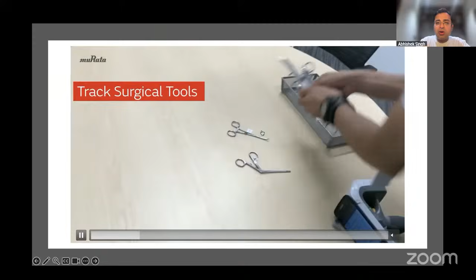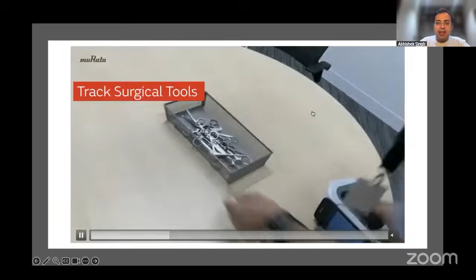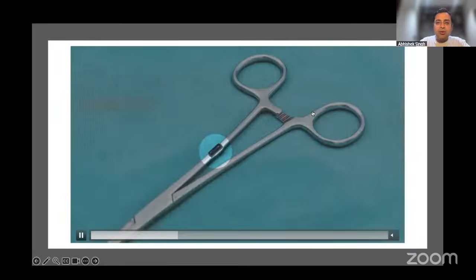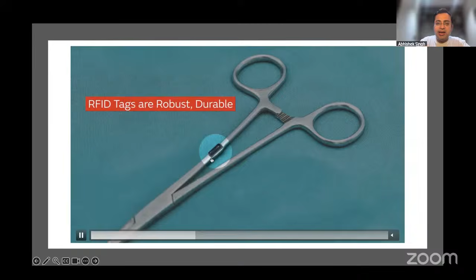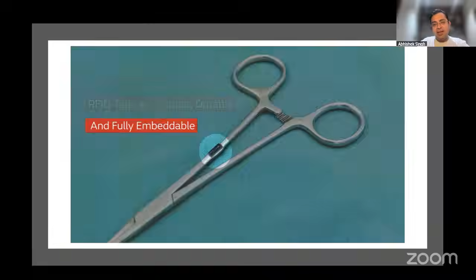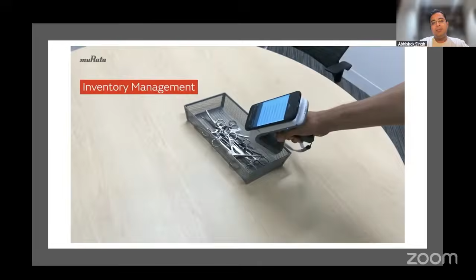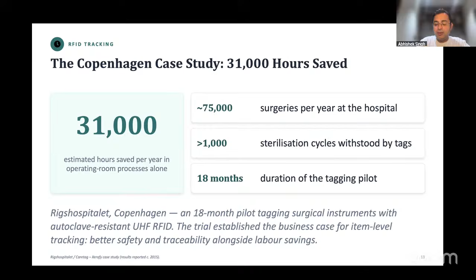So these are all RFID-tagged instruments, and with a scanner, these are the RFID tags which, as I told you, can last about 1,000 cycles of sterilization. And each tray can have about 60 to 80 items. So at the push of a button, you'll know how many items are there, how many times they have been reprocessed, what the position of the instrument in the cycle is, and when you tag this to a particular cycle, whether the cycle went through. When this was used in a Copenhagen case study, about 31,000 man hours were saved per year, out of a unit which had about 75,000 surgeries per year. Each tag lasted for 18 months and 1,000 sterilization cycles.